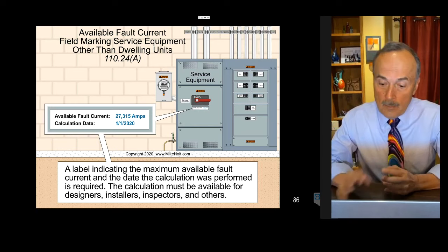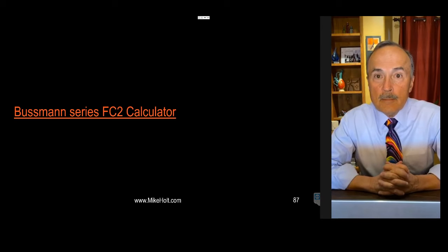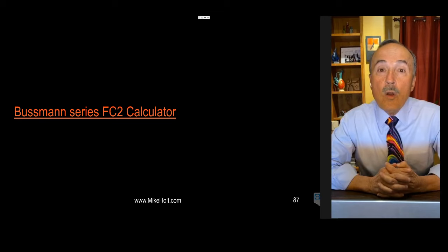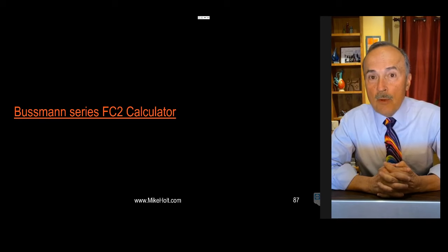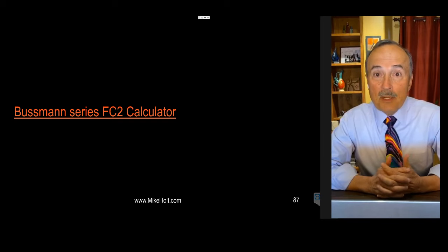So if it's not over 1200 amperes, you still have to put the available fault current calculation. You don't have to put the voltage. You don't have to put the time it takes for the protective device to open. You just have to do a calculation, stick that label on there, and put the date you did it. So how do you do the calculation?